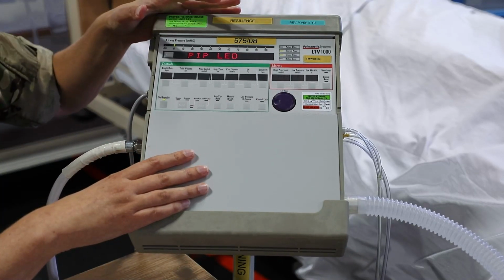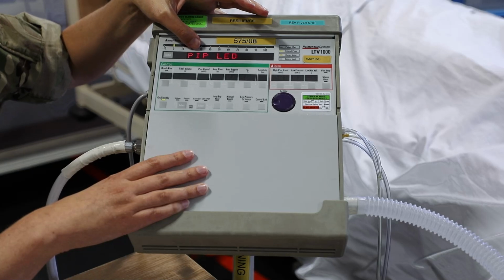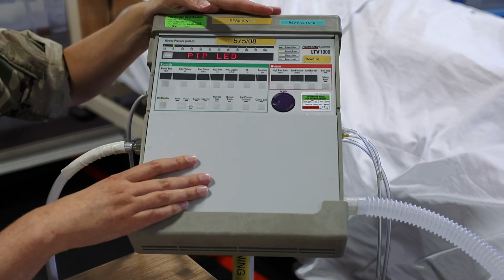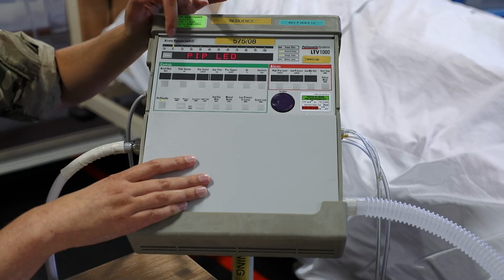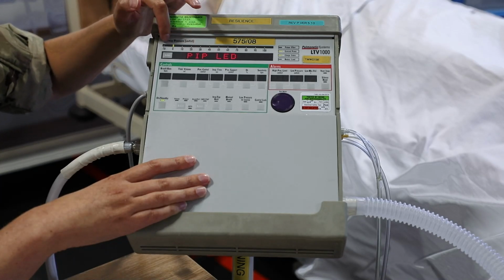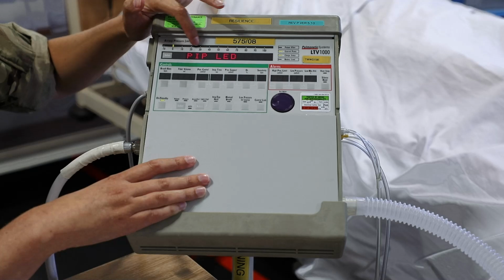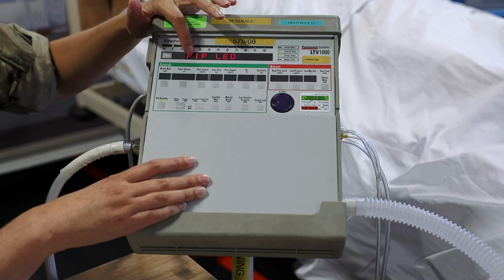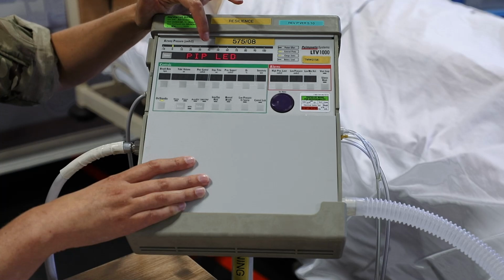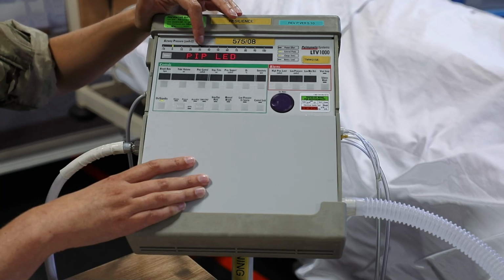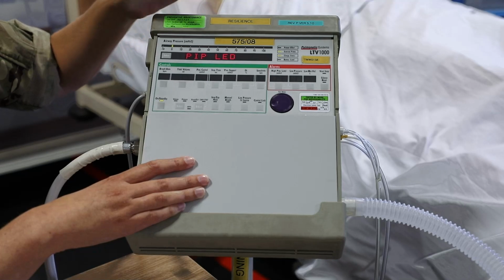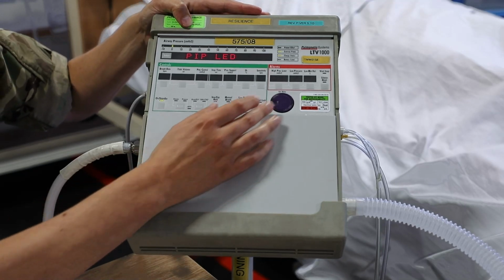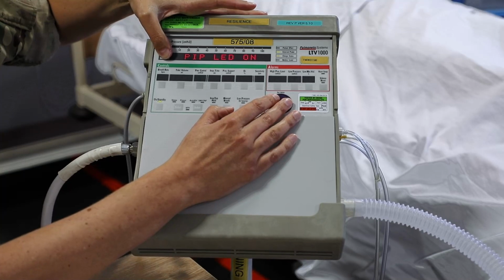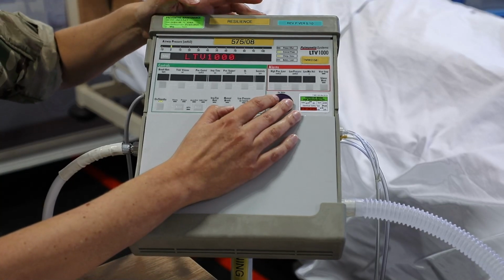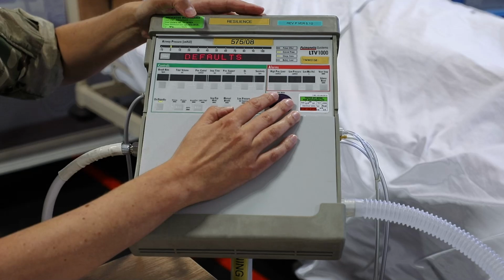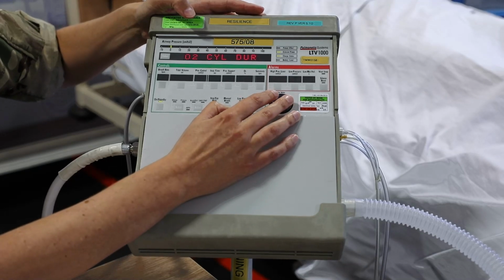Now this menu, this one hidden right at the end of the menu, is our peak inspiratory pressure LED. You would have seen from the orientation video that as the airway pressure increases, so you see this airway pressure barometer going up and down with each breath, this PIP LED function leaves a LED at the peak inspiratory pressure. So it's a really good visual indication of what the patient's peak inspiratory pressure is. So we would have this set as a default as on. Just scroll through the rest of these, don't select defaults.